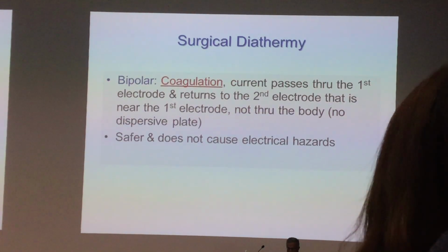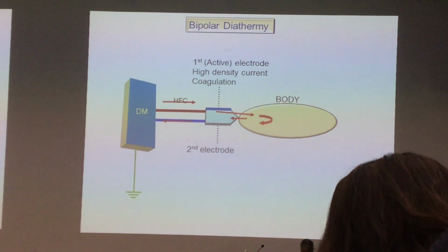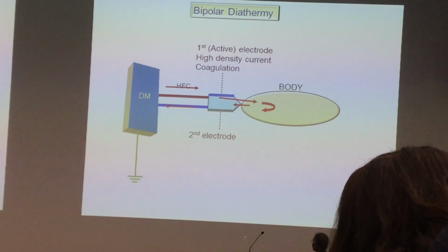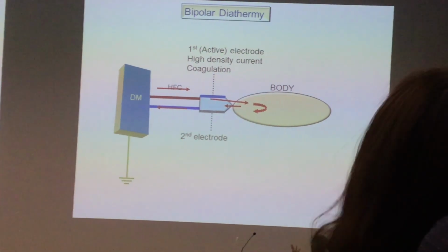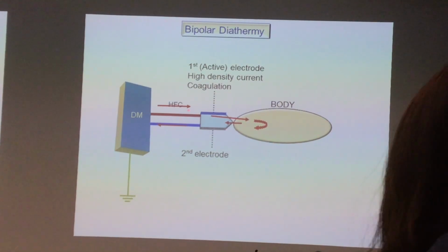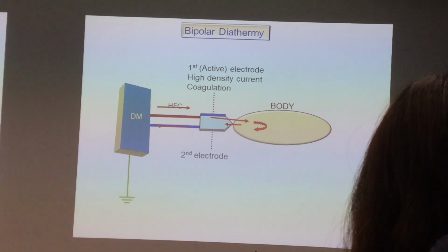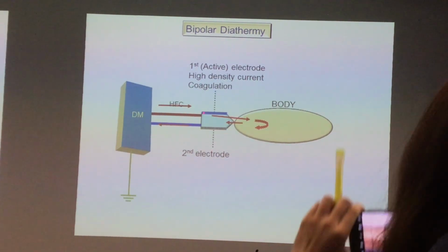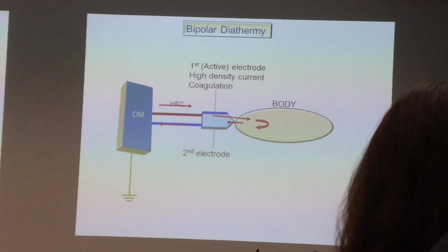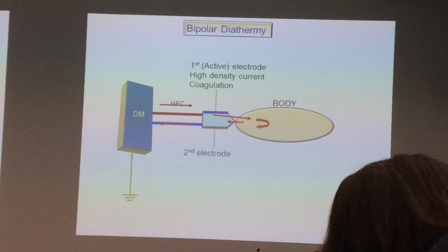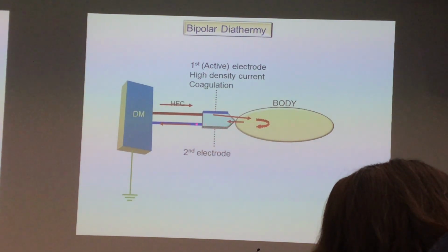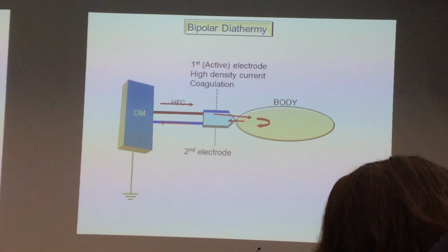Bipolar is only meant for coagulation. Bipolar, okay. Same, the current supply is high frequency current, 3 million. This is the probe, right? The probe. And the current doesn't go through the body, through the plate, back to the power supply. It only goes from the supply to the tip of the probe, then returns through the neutral. So the circuit is not complete because it doesn't go through the body fluid to the diathermy plate. So there's a difference between unipolar and bipolar.